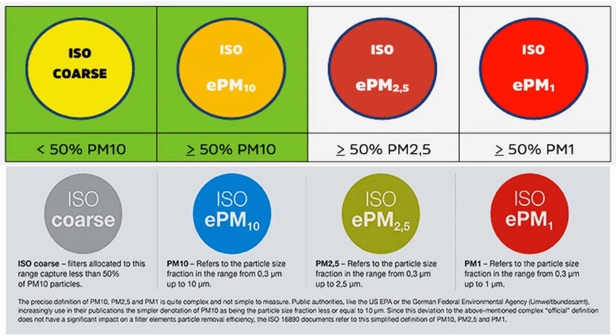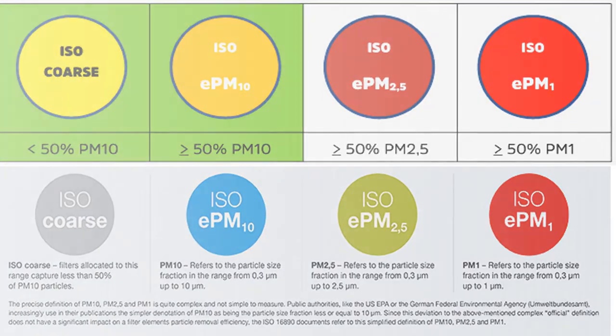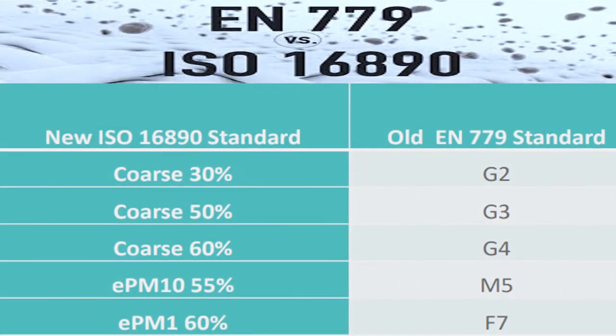Notes: E is the removal efficiency in the particle size range between 50 to 99% removal. Filters with removal efficiencies above 99% are tested to the ISO 29463 range of standards. This table shows the differences between the EN 779 and ISO 16890 standard — for example, Coarse 30% is equivalent to G2 filters. You can refer here for the different filter rating comparisons.